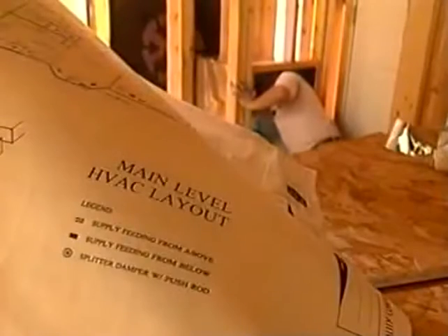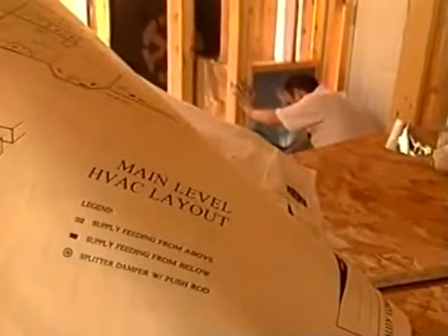Air leakage doesn't just happen on the supply side of a system. Sealing return ductwork is equally important. All joints in the return ductwork should be sealed with mastic. Every joint in the metal, every nail hole are all potential pathways for air leakage.